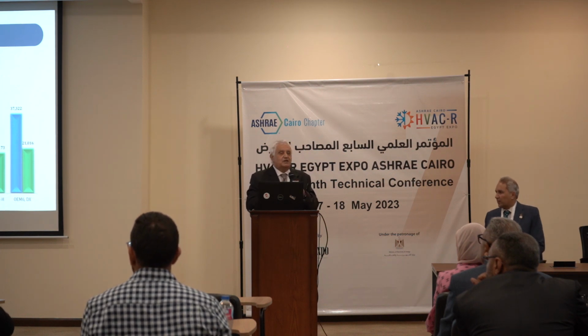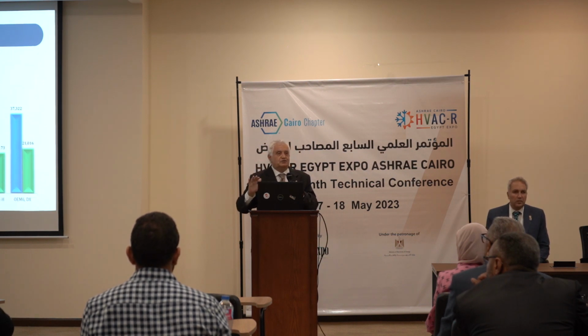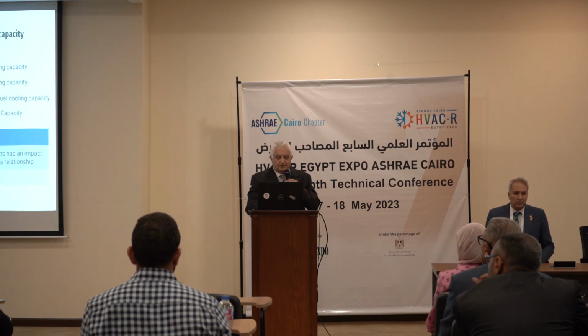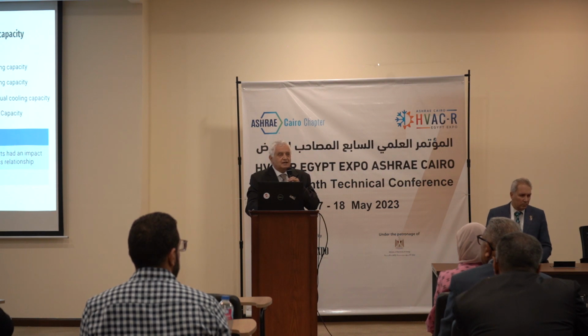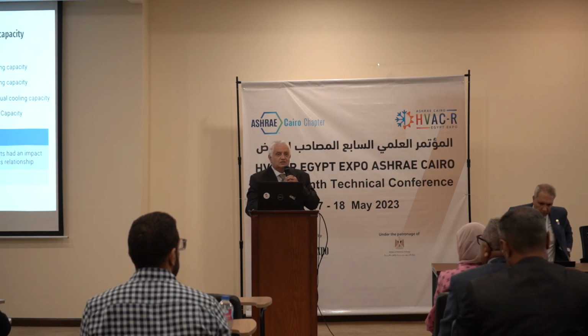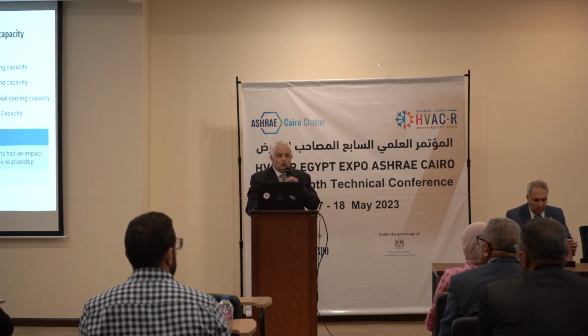So from either way you look at it, the test was successful for all 4 manufacturers. The EER was higher for the IEC machine than the DX machine, and the capacity was higher for the IEC machine than the DX machine. Does that mean we finished our test? No. We need to decide the size of the compressor, which varies from one manufacturer to the other. We didn't have the time to do that. So this is the next step, we hope.